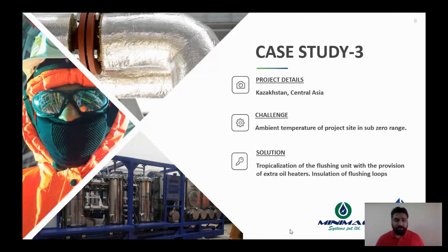Another important tip: insulation is needed for the pipelines or loops you want to flush. This is important because without insulating those pipelines, there would be a temperature fall during the flushing activity. So tropicalization and insulation of pipelines is important when flushing in severe ambient conditions with sub-zero temperatures.